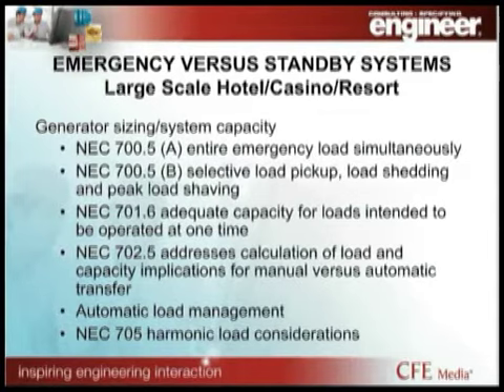So generator sizing and system capacity, again, 700 is very prescriptive. You've got to be able to pick up the entire emergency load simultaneously. 701 talks about adequate capacity for loads intended to be operated at one time, so it's kind of like a coincident peak evaluation. Then you get into 702, and they're really telling you, well, you need to run the typical calculations that you would run. On the medium voltage systems, a lot of times what we will end up doing is leveraging historical data and showing that to the authority having jurisdiction, so they understand that the connected load is X, but as Gerald referenced earlier, if you look at connected and you look at demand, you're anywhere from 30 to 40 to 50% of that calculated load as your actual running load. And if you size a 15 kV system for calculated load, nobody's going to be able to afford to build them, which is why the utility doesn't follow that approach and actually falls under a different code in terms of how they size. It's not based on NEC.